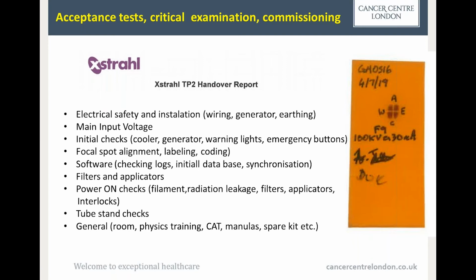All electrical parameters were checked, whether the cooler was working, whether emergency buttons and warning lights were working, because these are safety-related checks. Really, it was like a table with tick boxes, following quite a big document and verifying that the system is working safely in terms of installation, electrical aspects, as well as software and all warning lights and so on. Also, we checked that our filters and applicators were working, recognized, and named properly, so that we could not have any contradictory information.